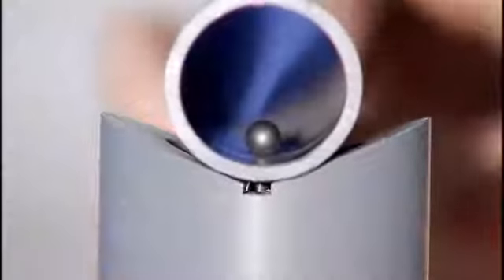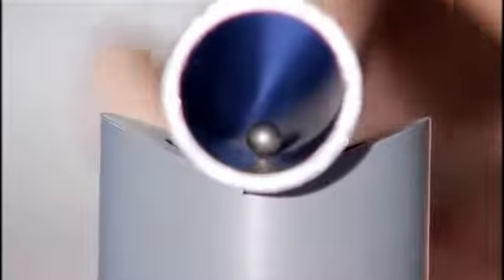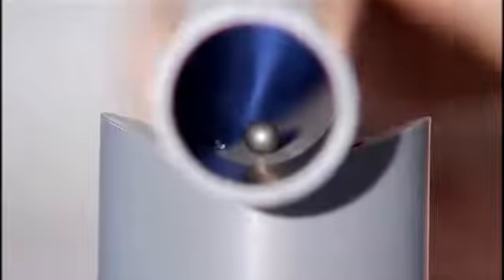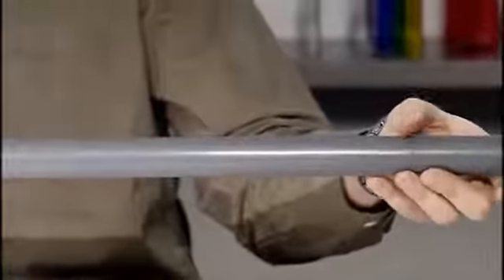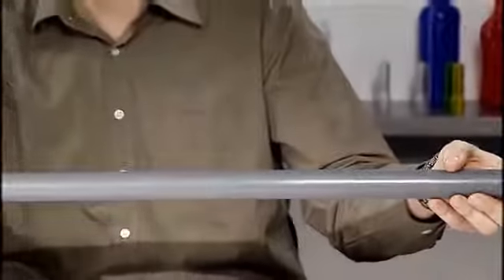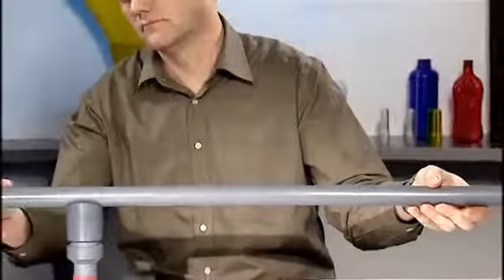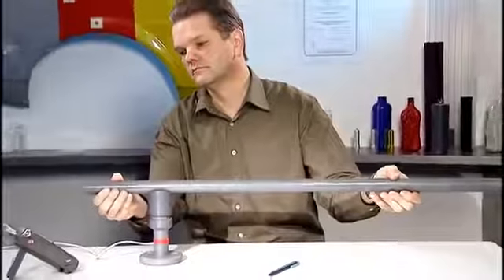The MiniTest 7200FH and 7400FH gauges use a steel ball attracted by the magnetic sensor to measure the wall thickness of a sample. The change of magnetic field lines is converted into the thickness of the sample.